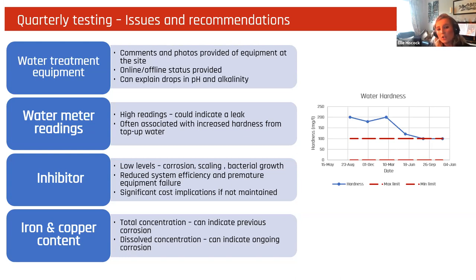Another issue that we flag on site is high levels of water hardness. It's typically associated with systems that have higher levels of makeup water being added. So our recommendation is typically to install a pre-treatment plant, such as a water softener, on the boosted cold water entering the system. But sometimes systems just require more makeup water than others, though significantly high levels could indicate a leak on the system.